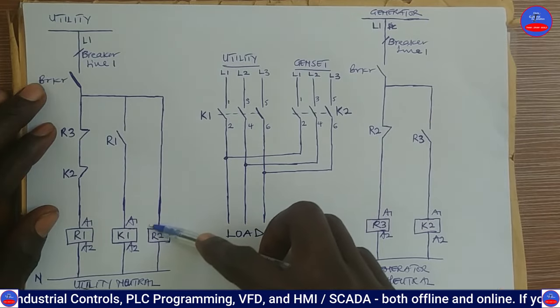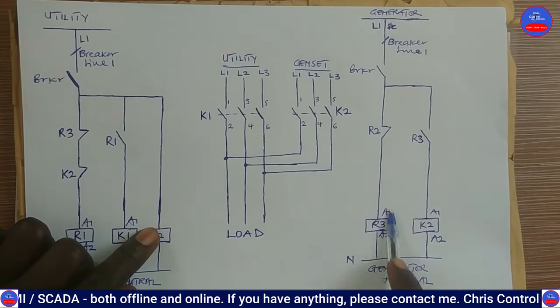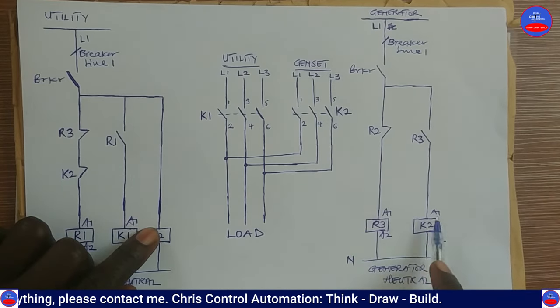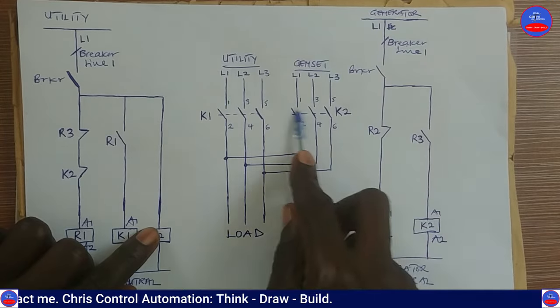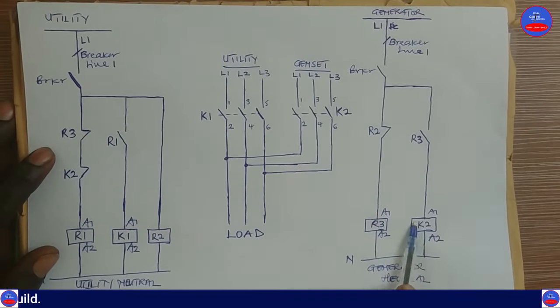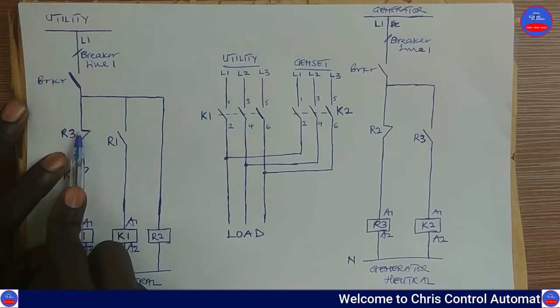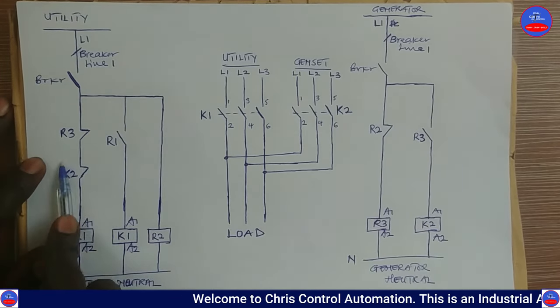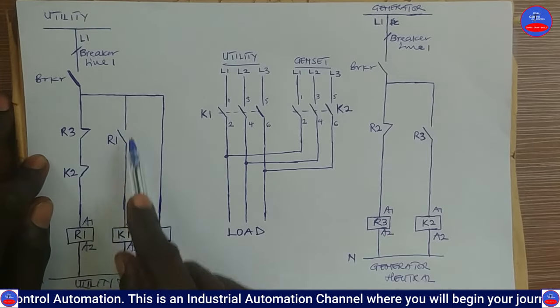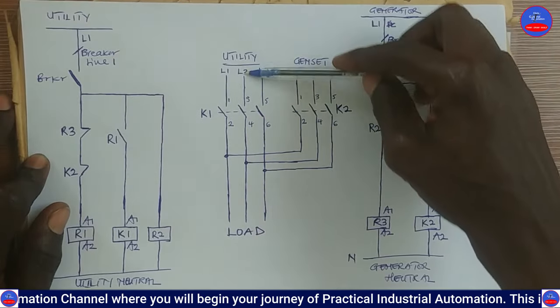R2 energizes through the utility line. When R2 energizes, it opens its contact, which causes R3 to de-energize. When R3 de-energizes, its contact opens, which causes K2 to de-energize. When K2 de-energizes, its contacts open and the generator power is cut off. At the same time, as K2 and R3 de-energize, their contacts close back, allowing R1 to energize again. R1 energizes, closes its contact, K1 energizes, its contacts close, and the utility power is applied back to the load.